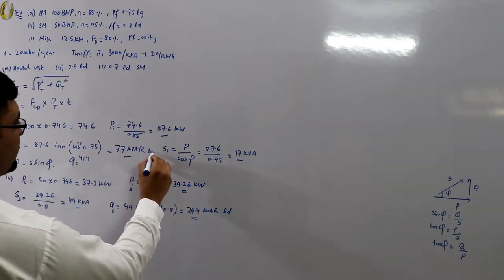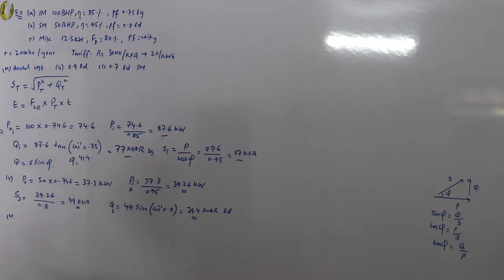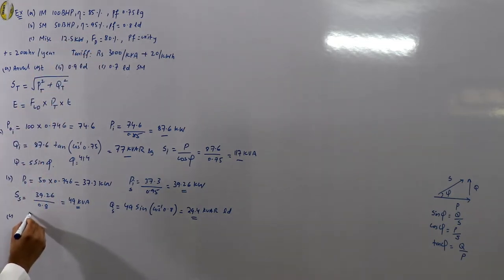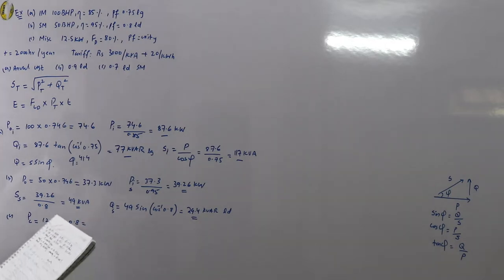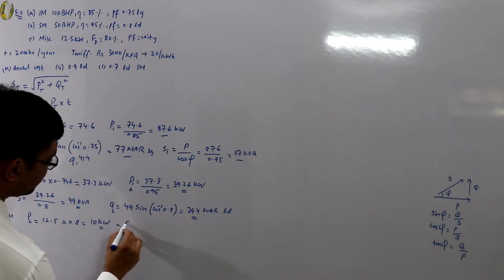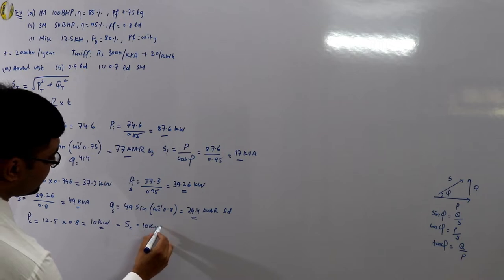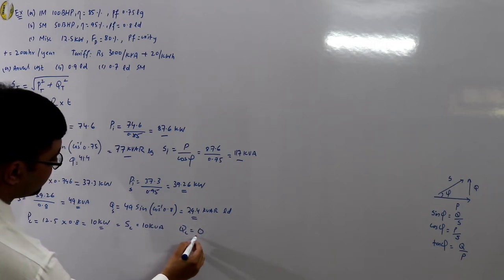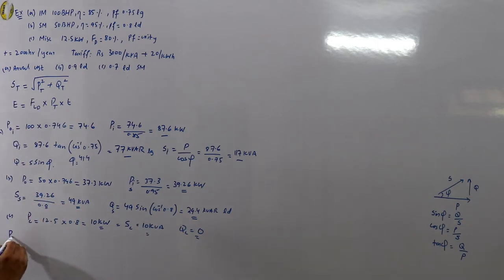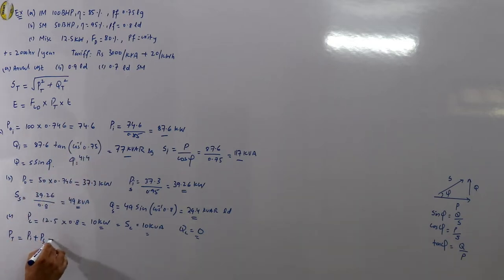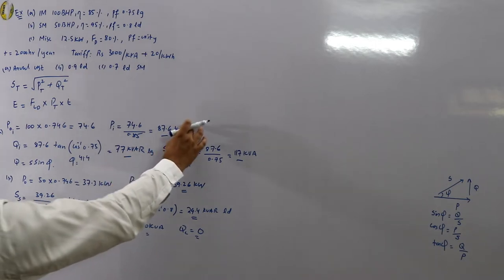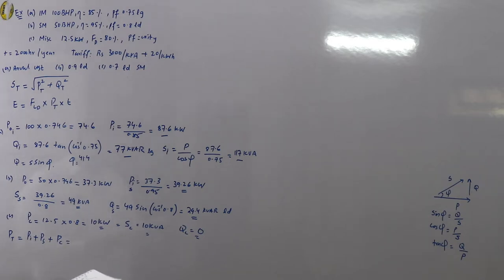For Load C — the miscellaneous load — the maximum demand P_c = connected load × demand factor = 12.5 × 0.8 = 10 kilowatts. S_c = 10 kVA and Q_c = 0, since power factor is unity. P_total = P_i + P_s + P_c = 87.6 + 39.26 + 10 = 137 kilowatts.